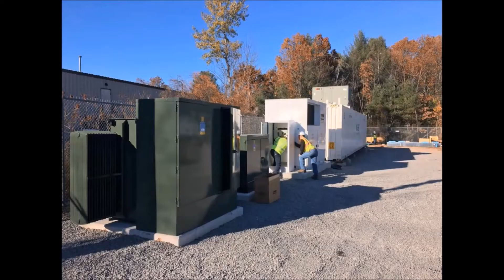Here, with these same pads, if you look to the front, that's the main transformer connected into the battery system, or the inverter, where the second to last white container is. The transformer after that is the small auxiliary transformer I mentioned, on that small pad. The two gentlemen working are at the inverter, where the 13.8 to 480 volt inverter changes the voltage, whether we're charging from 13.8 to 480 or discharging from 480 out to our 13.8 system. The last piece of equipment you see is the actual batteries.